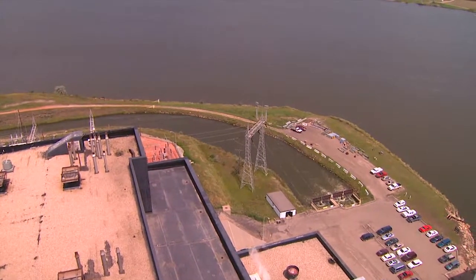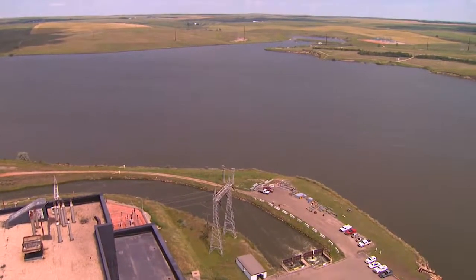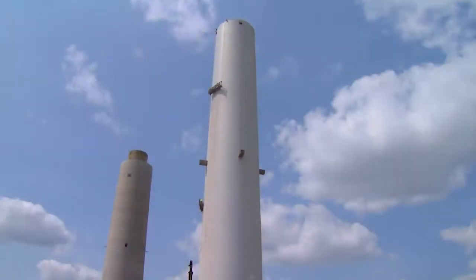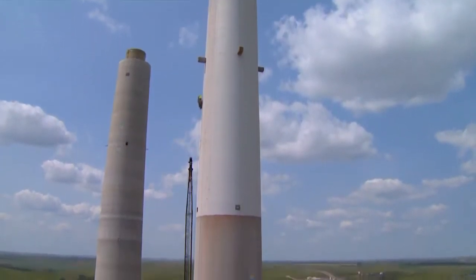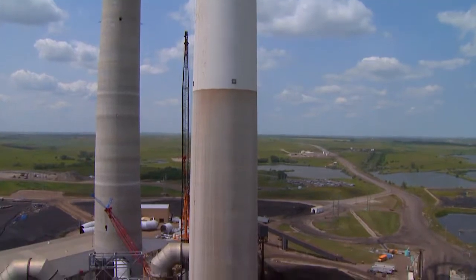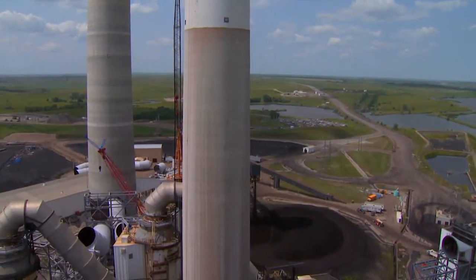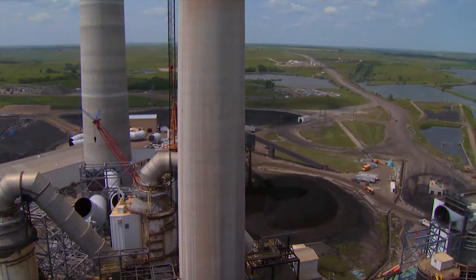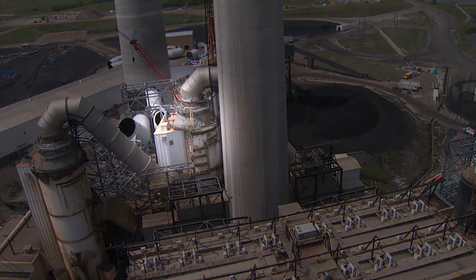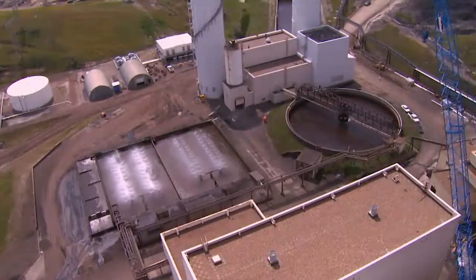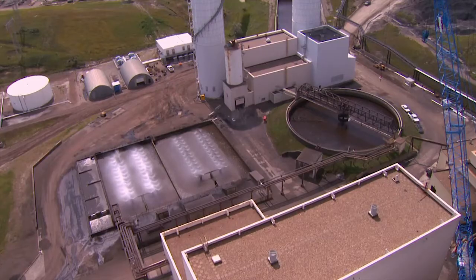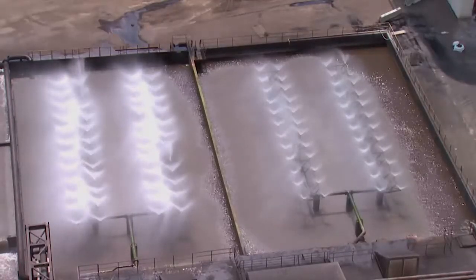Condensing steam to a liquid is the biggest use of water in a thermoelectric plant. Additional water is needed to remove sulfur from the flue gas, the exhaust from burning coal to make steam. There is sulfur in our fuel, so the flue gas coming out of the boiler has sulfur, and we run that through a wet scrubber, a large tower. An alkali slurry removes the sulfur from the flue gas. The water used in the scrubber is cycled back and reused.